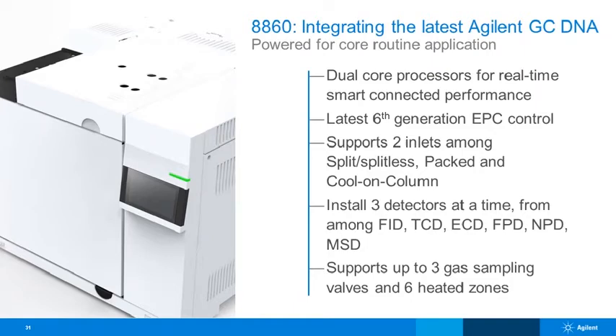So as already said before, it's got a dual core processor on board for real-time checking and the connection. The 6th generation EPC that I mentioned, with the leak checking from the Intuvo, supports 2 inlets, which can be a mixture of split-splitless, packed or cool-on-column, and 3 detectors at a time. So you can have 3 detectors on this GC, a mixture of FIDs, TCDs, ECDs, FPDs, NPDs, and MSD. And should you be doing gas sampling, you can have up to 3 gas sampling valves and 6 heated zones.